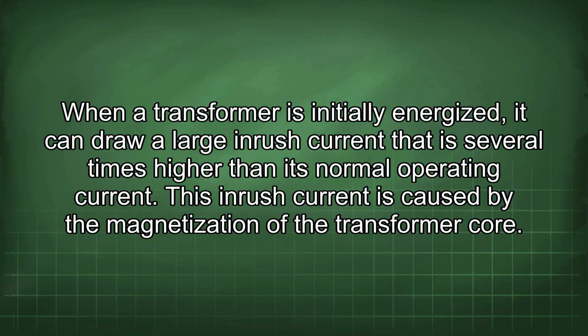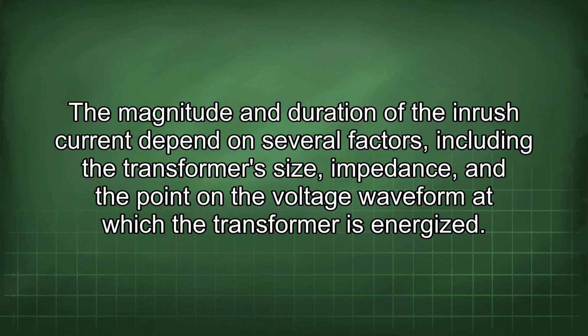When a transformer is initially energized, it can draw a large inrush current that is several times higher than its normal operating current. This inrush current is caused by the magnetization of the transformer core. The magnitude and duration of the inrush current depend on several factors, including the transformer size, impedance, and the point on the voltage waveform at which the transformer is energized.